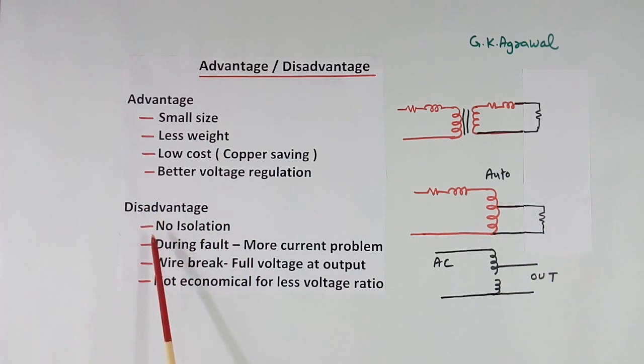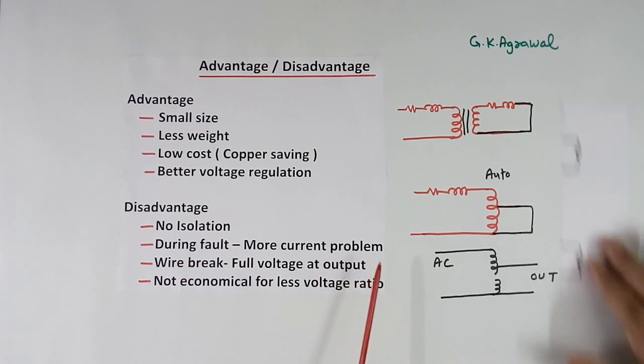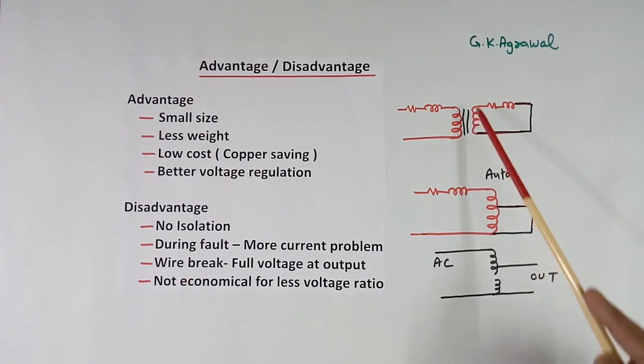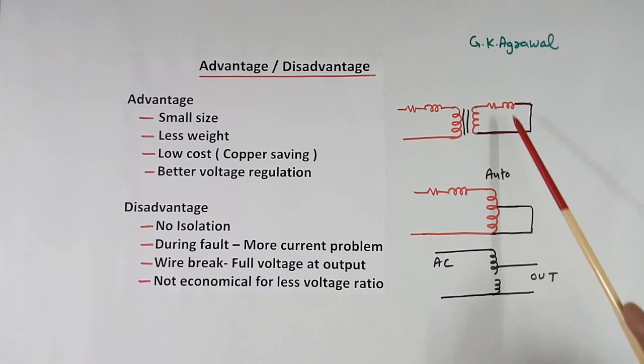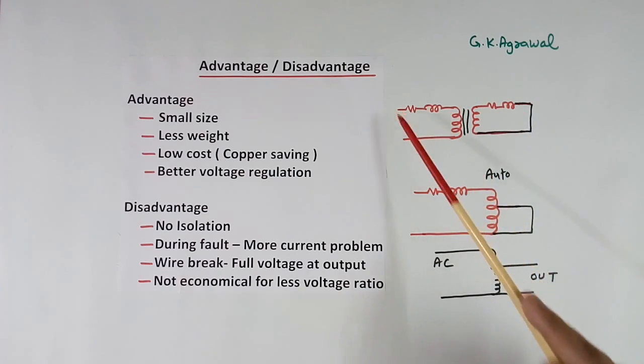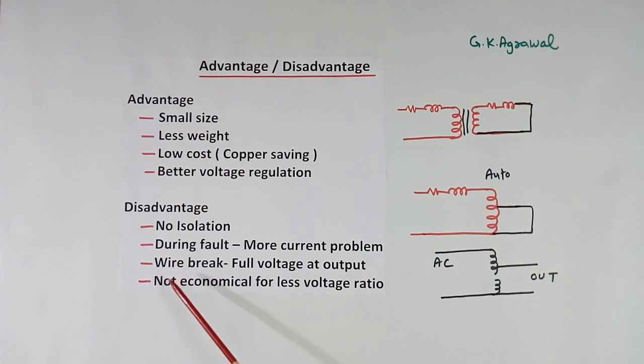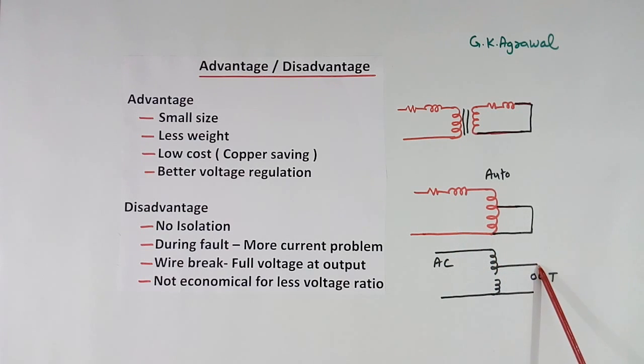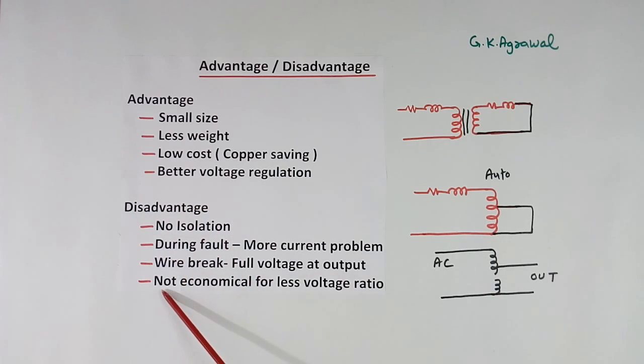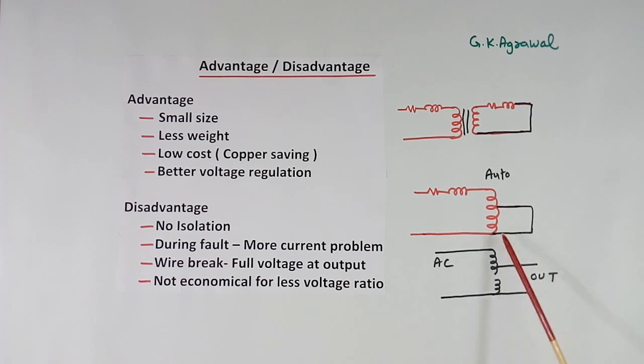Disadvantages: no isolation. During a fault, there is a more current problem. If the output gets short circuited, in a normal transformer the current is limited by both the primary and secondary impedances. In an auto transformer there is only 1 impedance to limit the current, so more current will flow. Also, if a wire break occurs, full voltage will appear at the output; if there is a capacitor, voltage will go up further. Additionally, it is not economical for a low voltage ratio at the secondary.